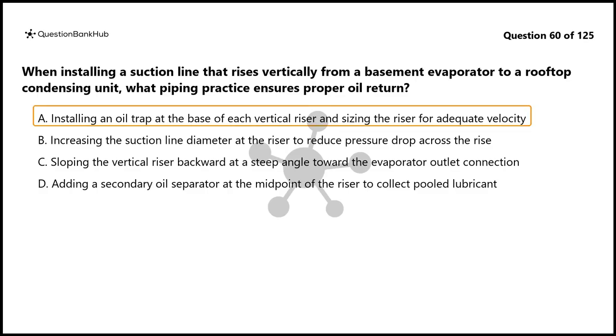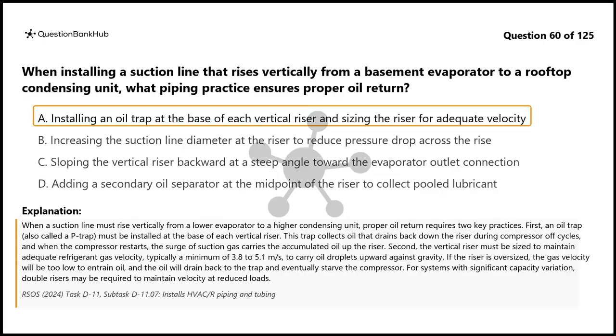The correct answer is A. When a suction line must rise vertically from a lower evaporator to a higher condensing unit, proper oil return requires two key practices. First, an oil trap, also called a P-trap, must be installed at the base of each vertical riser. This trap collects oil that drains back down the riser during compressor off cycles, and when the compressor restarts, the surge of suction gas carries the accumulated oil up the riser.